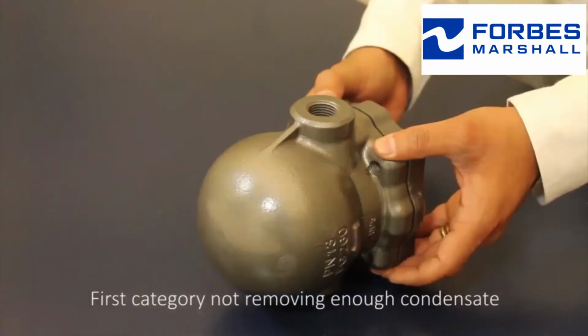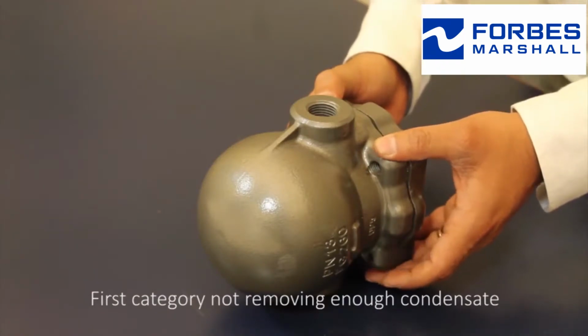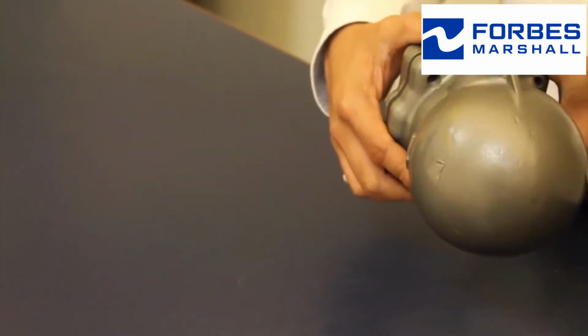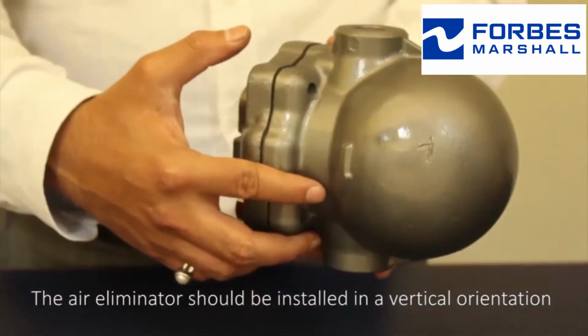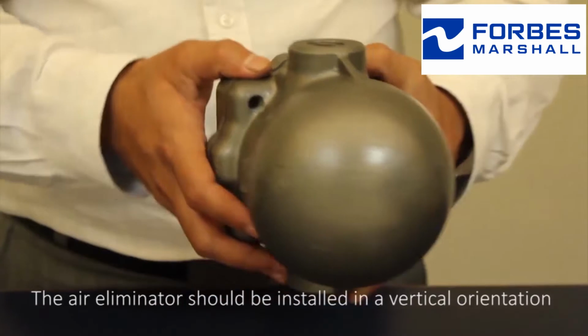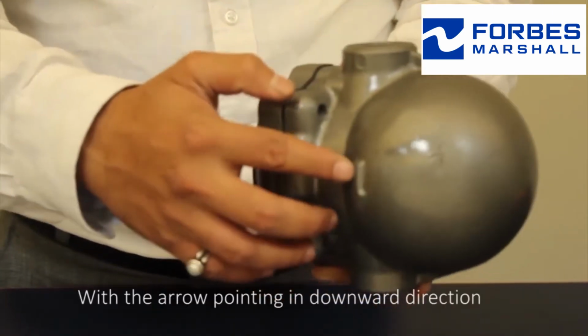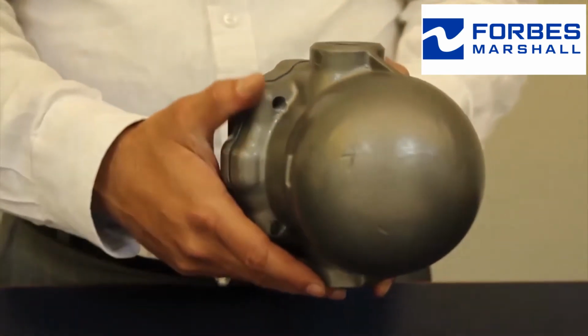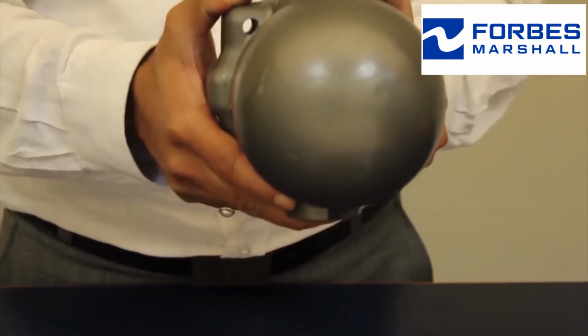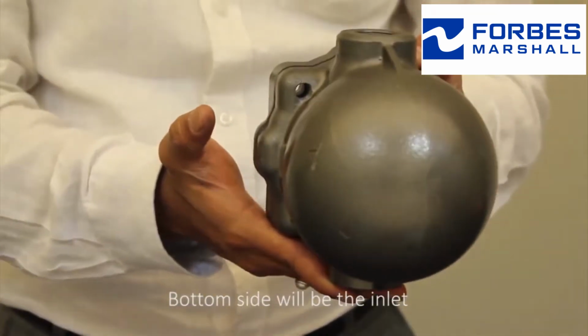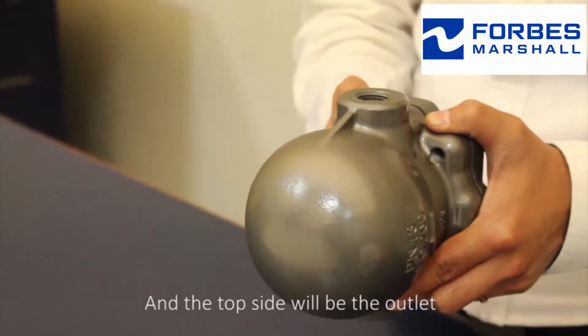The first category, not removing enough condensate. Check the trap installation. The air eliminator should be installed in a vertical orientation with the arrow pointing downward. The bottom side will be the inlet and the top side will be the outlet.